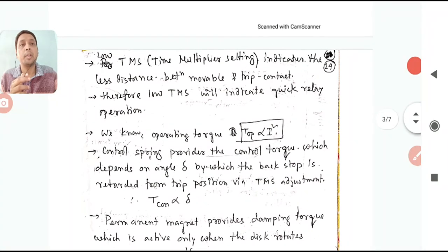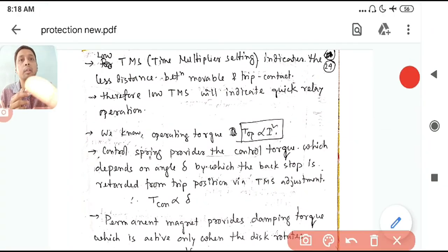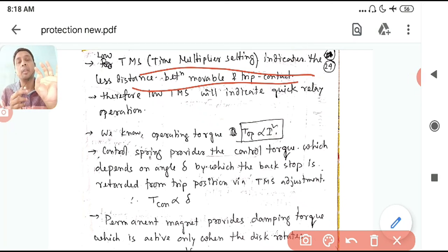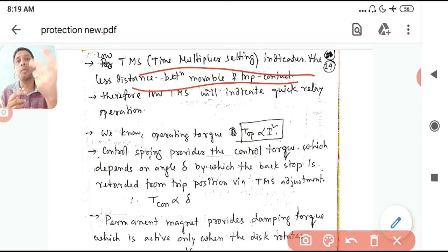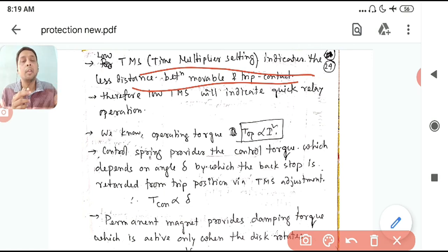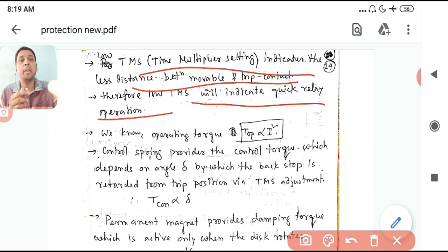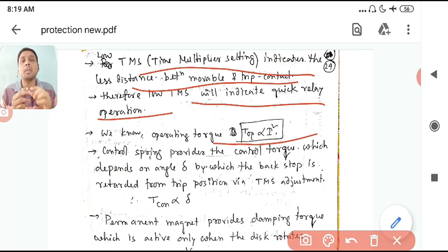Low TMS indicates less distance between the movable disc and the trip contact. If TMS is 1, the disc takes a full rotation to reach the contact. If TMS is 0.5, it is at half rotation and trips sooner. Therefore, low TMS indicates quicker relay operation — lower TMS gives lower operating time.